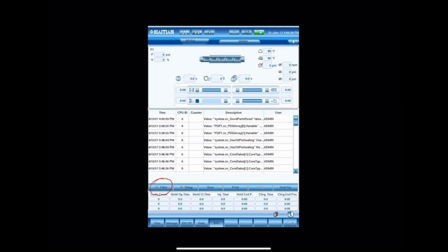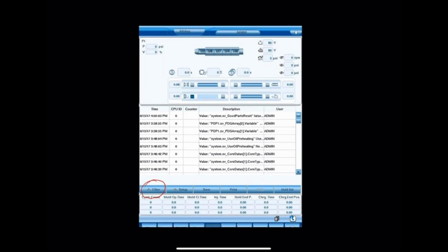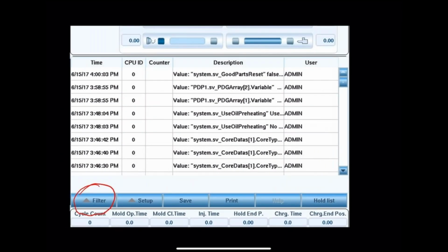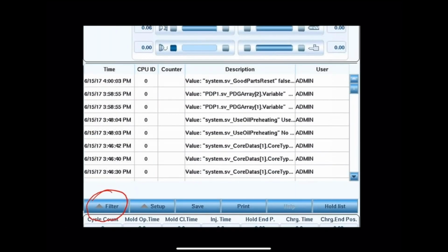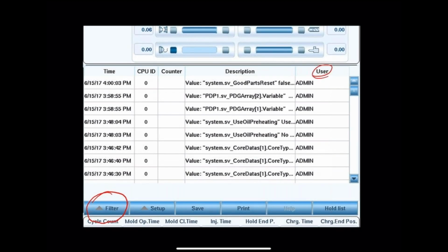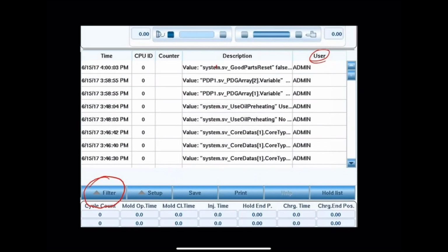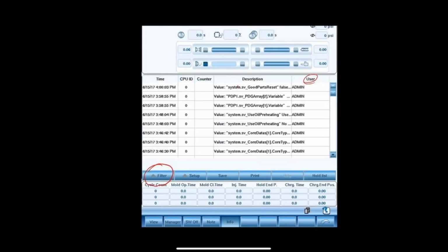And in manager info, you have a filter here. So what this manager does, it tells you all your changes and your alarms. So if you change that filter and say you want to look at all the alarms, you can then look at all the alarms. Right now it's showing you all the changes that happened and who changed them. So if you highlight that, it'll actually show you the full value down at the bottom. You can have a good readout of it, so you'll know exactly what it was. For example, this guy here, they turned the preheating to no, and over here they turned it on to use.